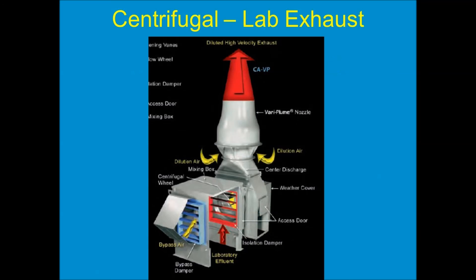Again, same principle — small blades attached to a ring, rotation creates low pressure in the center. Centrifugal impellers are also used in laboratory exhaust fans. In this case we have a blower where the air comes in horizontally through the bypass section mixing box, then into the inlet of the fan. The impeller, shown in yellow, is just behind the isolation damper shown in red. The air is drawn into the fan, turns 90 degrees off the wheel, follows the shape of the fan housing straight up, and since it's lab exhaust, it has an induction-type nozzle on top to dilute the air and achieve a high plume. In our next segment we're going to talk about fan curves and the fan laws, so please stay tuned.